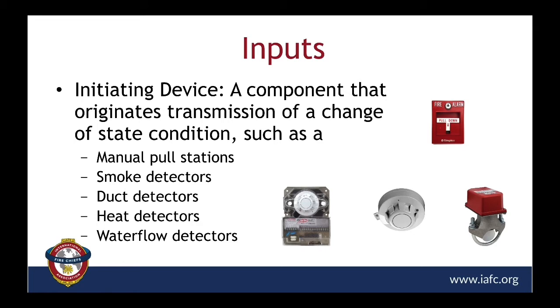All right, let's look at the input devices. Do a little deeper dive in here. A fire alarm system is activated by initiating devices that act as inputs to the fire alarm control unit, and they are either manually or automatically activated. So let's take a closer look. Manual fire alarm activation is achieved through the use of a pull station that requires human intervention. So in its simplest form, the user activates the pull station by pulling down the handle, which completes the circuit and locks the handle in the activated position, and it then sends an alarm signal to the fire alarm control unit.